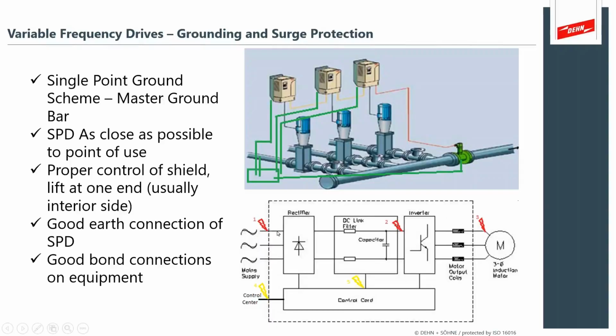And then where does it appear? Where does a surge protection device need to go when you're between a variable speed drive and a motor? Do you want it next to the motor? Do you need it next to the output of the inverter? There are also discussions about the length of these cables. Are they greater than 10 meters, where you'll need protection on both ends of these devices?